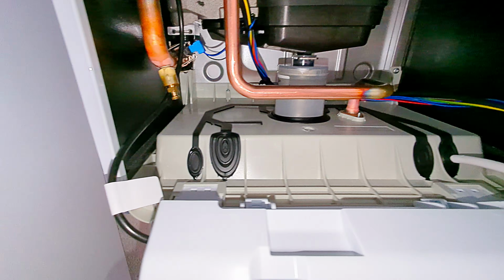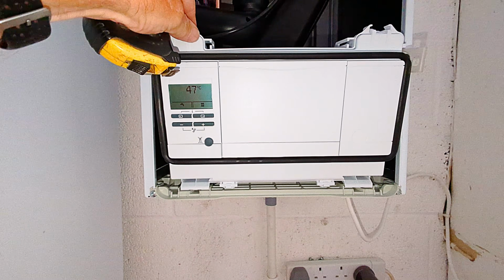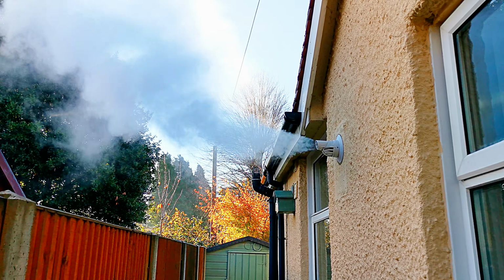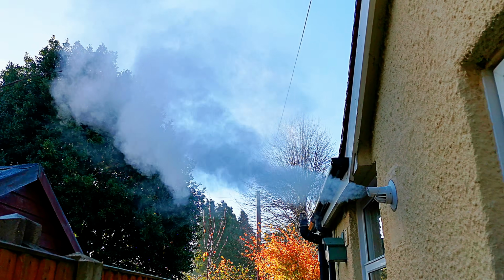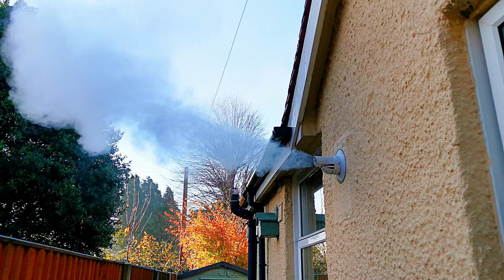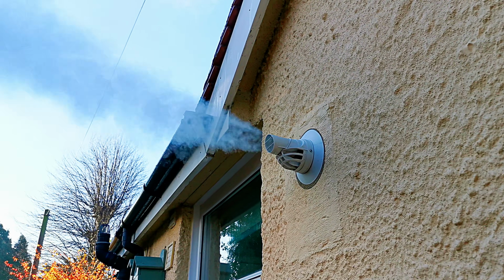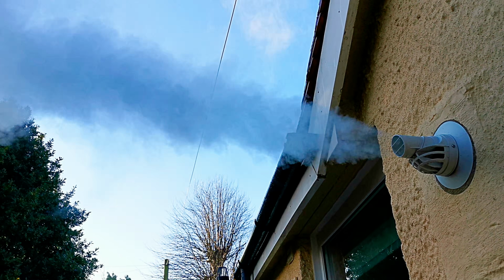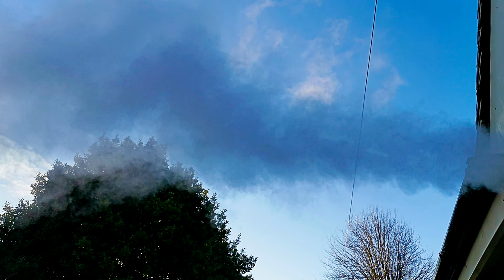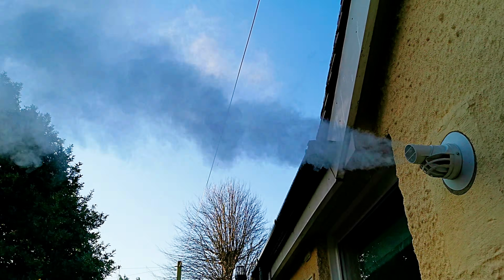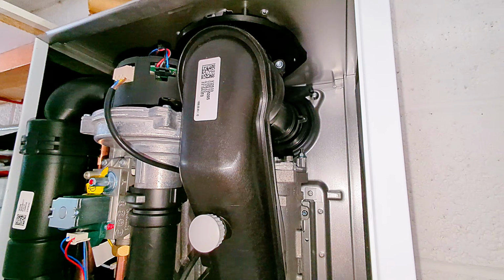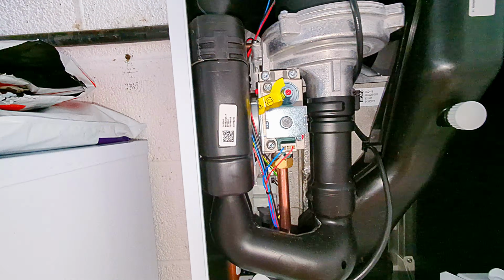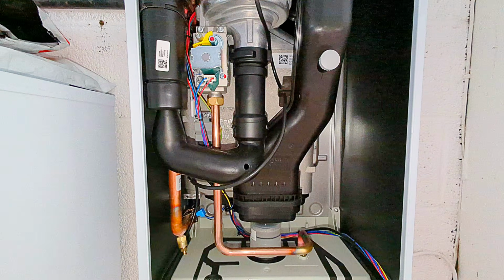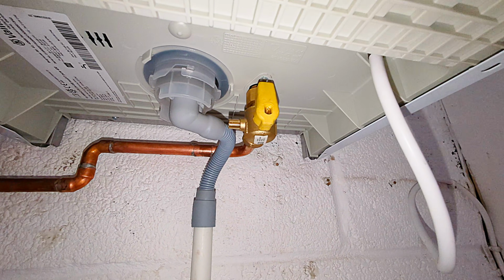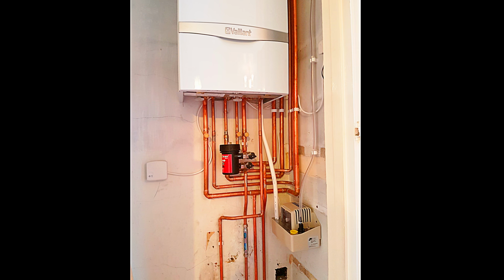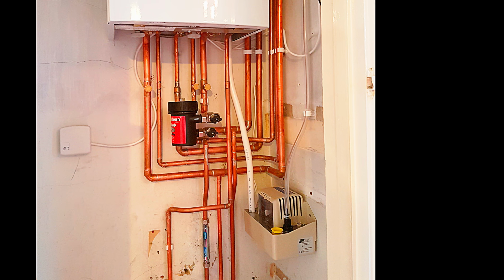And that water vapour is holding a lot of heat. So a new modern condensing boiler will extract that heat from that water vapour, making the boiler really efficient. When I say water vapour, it's like steam, but you can't see the water in the vapour that's being produced from burning the gas. But if we extract more heat out of those flue gases, that allows the water vapour in the flue gases to condense, which means it's turned back into water, and that condensed water runs down through the heat exchanger, where more heat is extracted from that water, making the boiler more efficient. The condensed water then runs into the waste condensing system, where it's then disposed of outside the boiler.